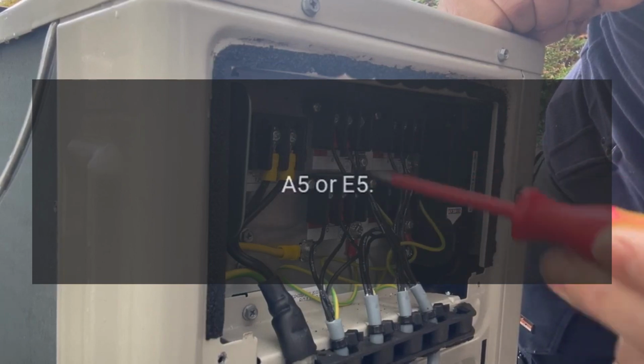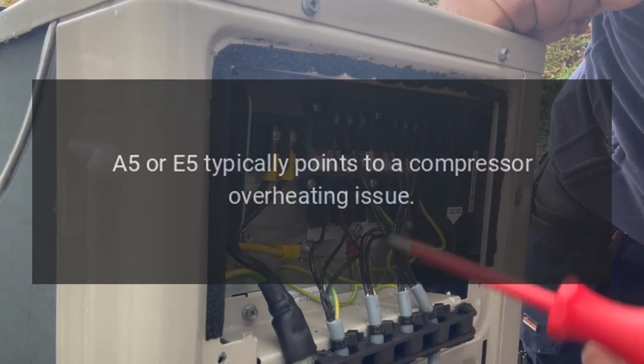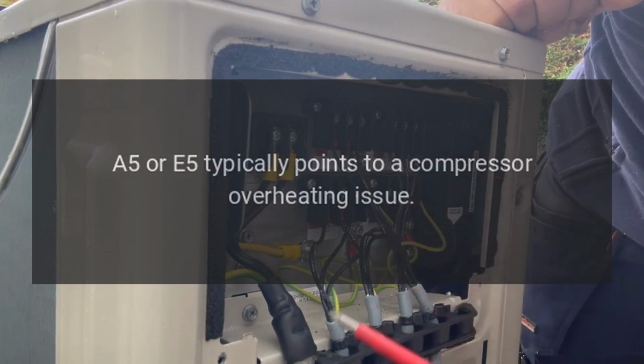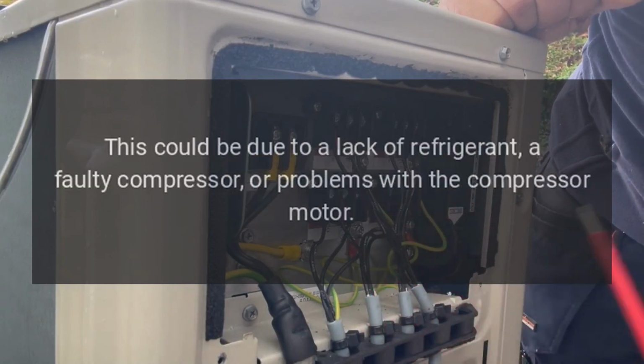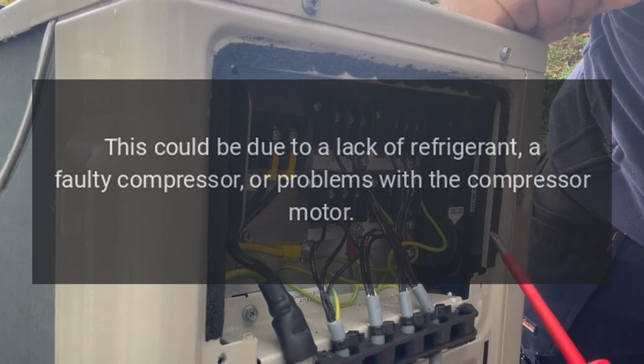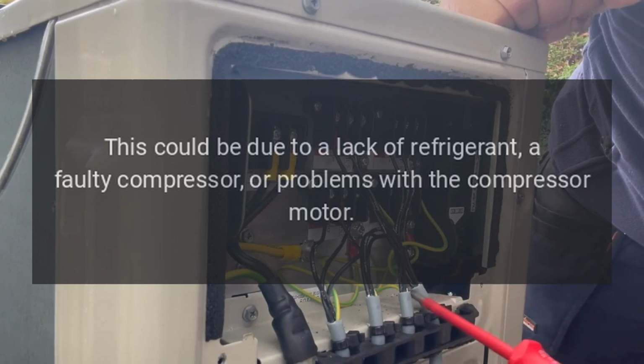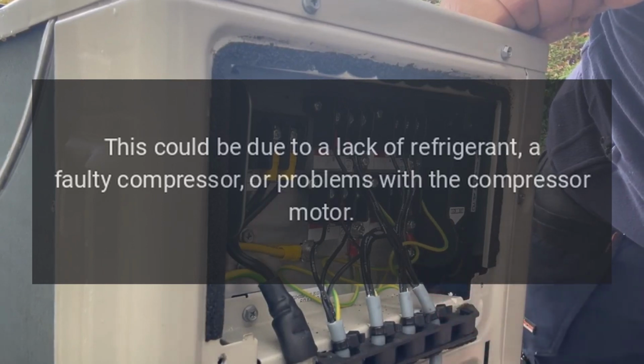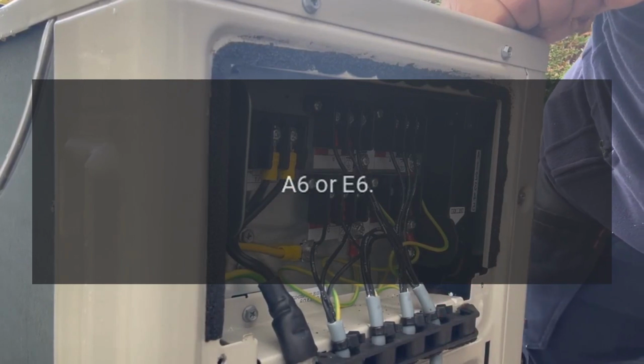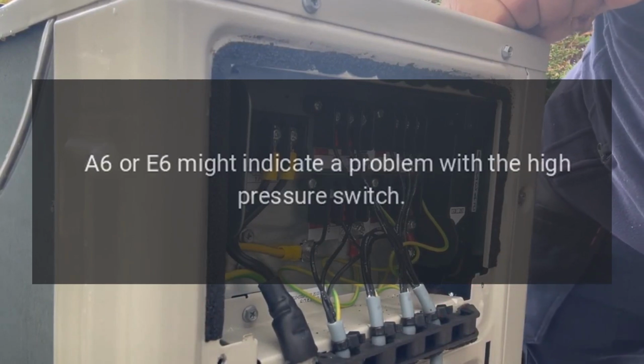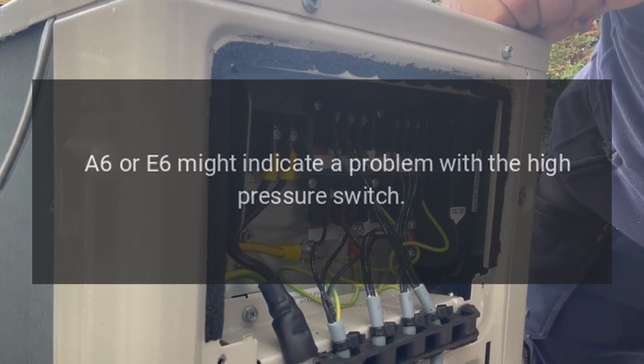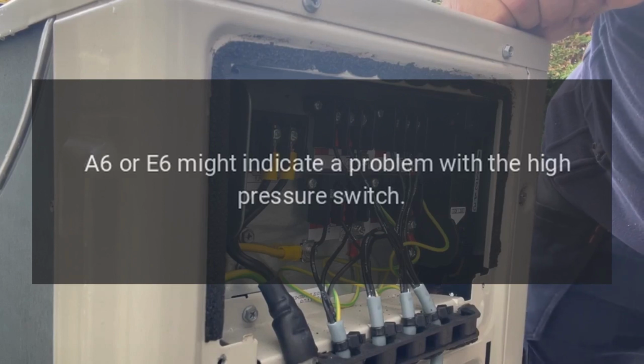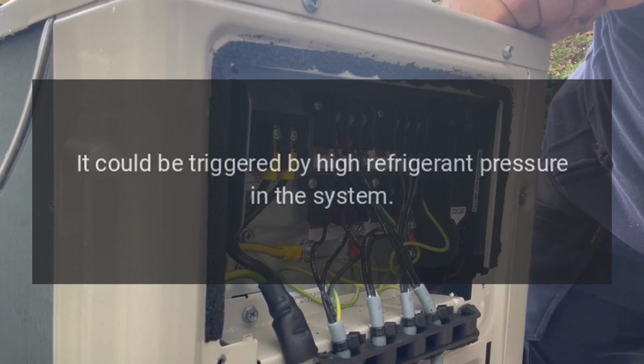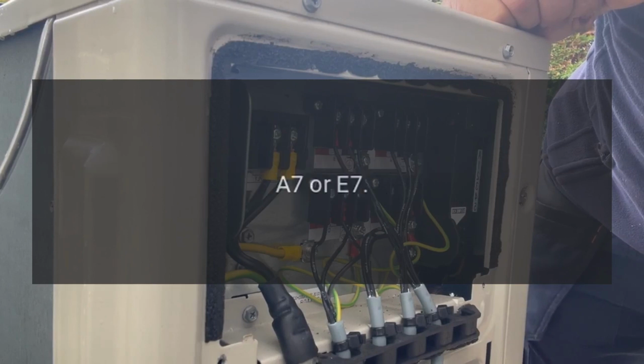A5 or E5. A5 or E5 typically points to a compressor overheating issue. This could be due to a lack of refrigerant, a faulty compressor, or problems with the compressor motor. A6 or E6. A6 or E6 might indicate a problem with the high-pressure switch. It could be triggered by high refrigerant pressure in the system.